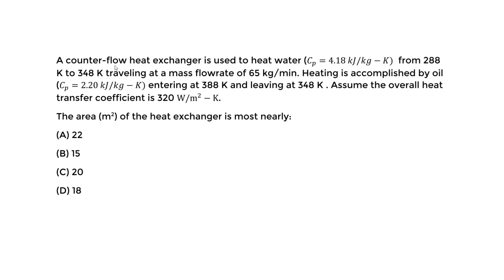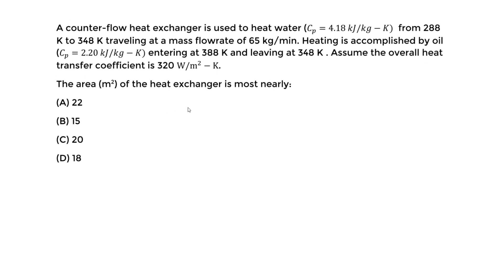Heating is accomplished by oil with a specific heat capacity of 2.20 kJ per kg Kelvin. The oil is entering at 388 Kelvin and leaving at 348 Kelvin. We assume the overall heat transfer coefficient U is 320 watts per meter squared Kelvin. What we want to find first is the area of the heat exchanger that would satisfy these conditions.